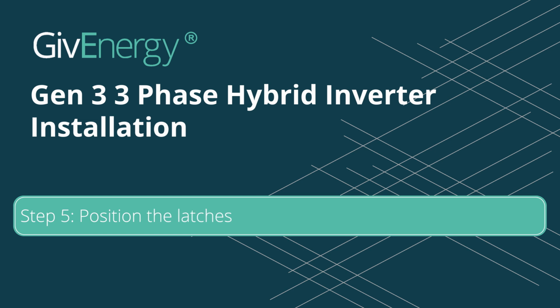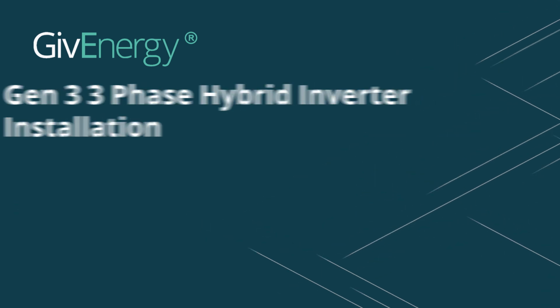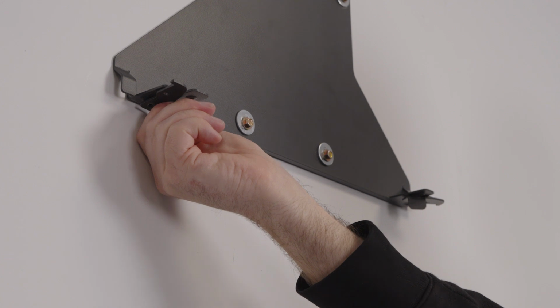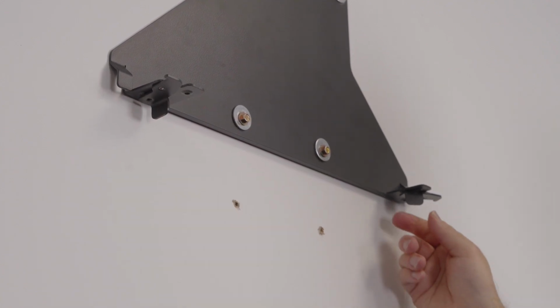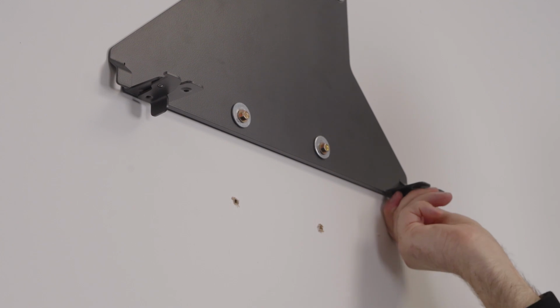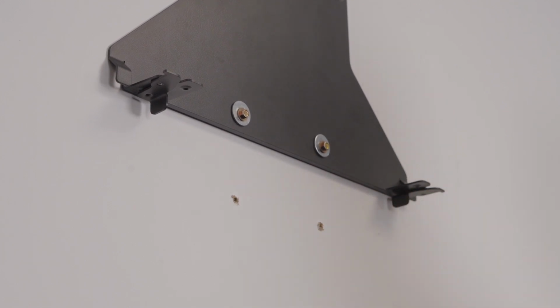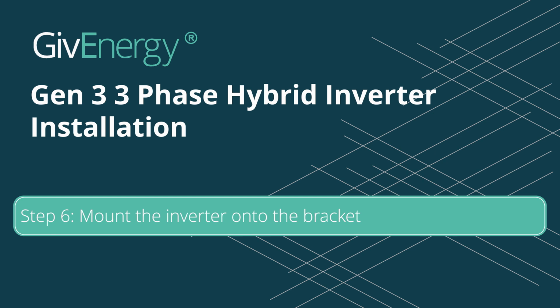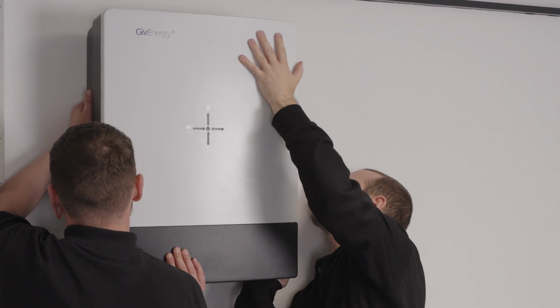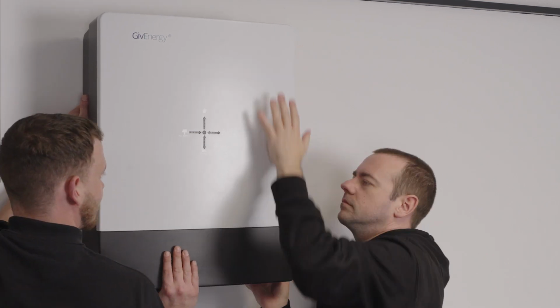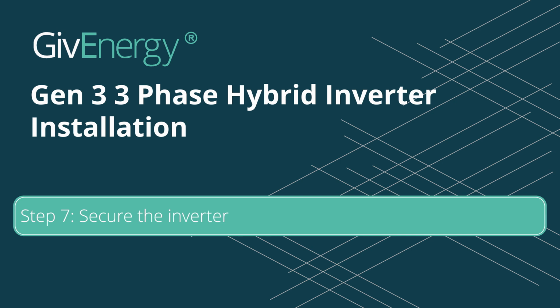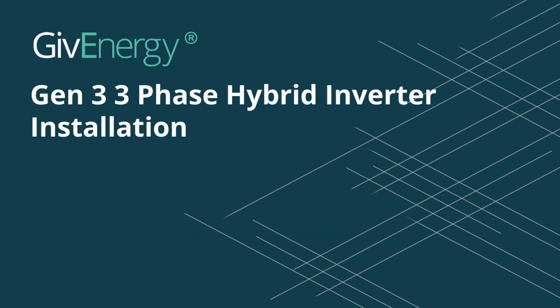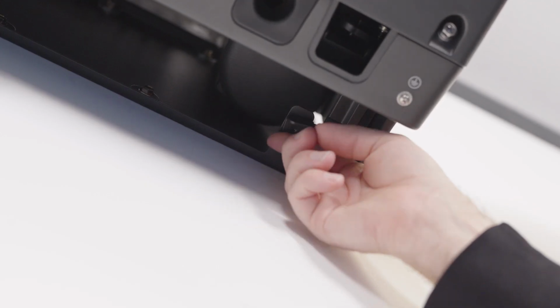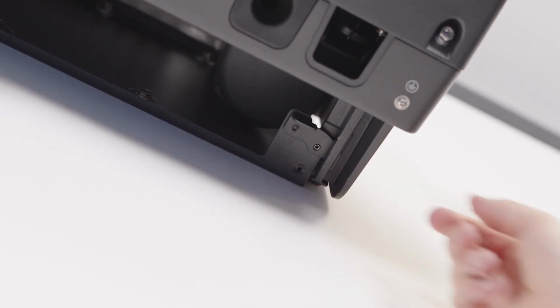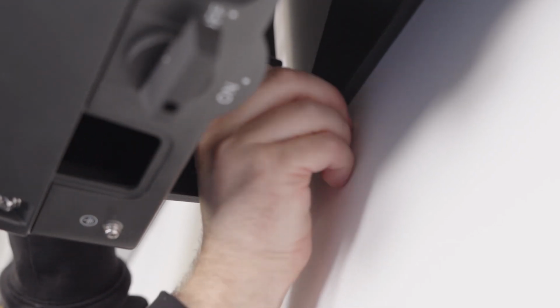Step 5. Position the latches. Once the mounting bracket is in place correctly, you need to position the latches to hold the inverter securely in place like this. Step 6. Mount the inverter onto the bracket. Mount the inverter onto the bracket, ensuring you're following manual handling best practices. Step 7. Secure the inverter. Once the inverter is on the bracket, secure it in place using the latches that are behind the unit at the bottom like this.